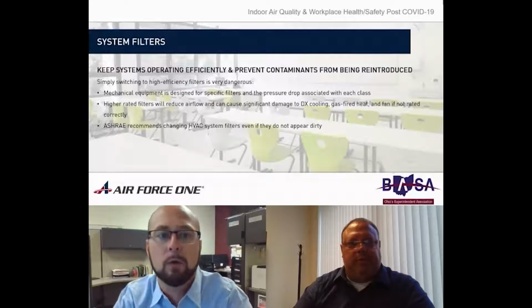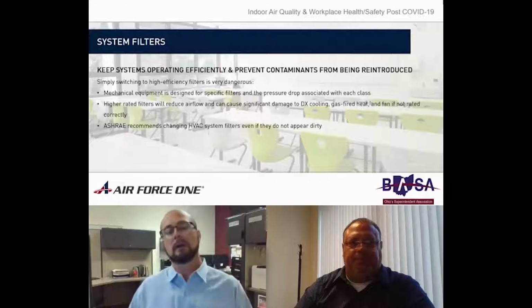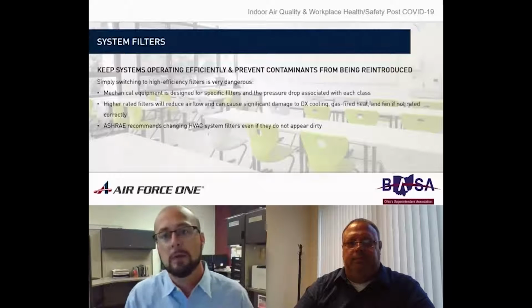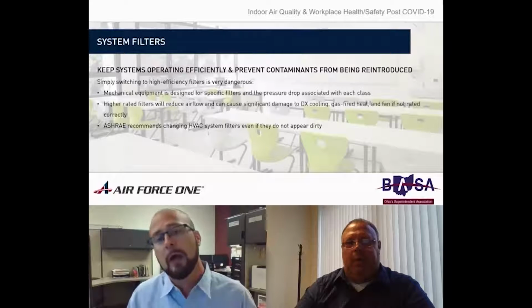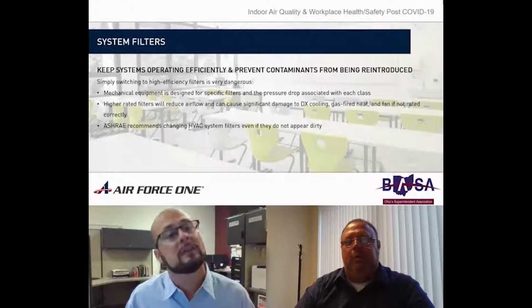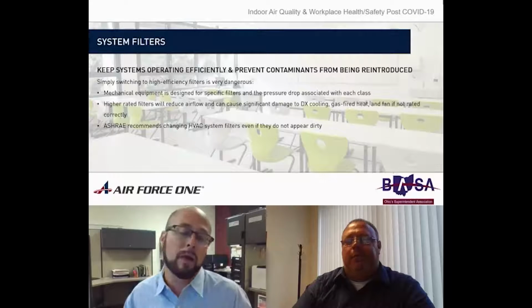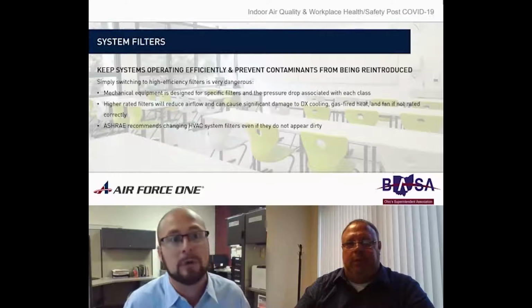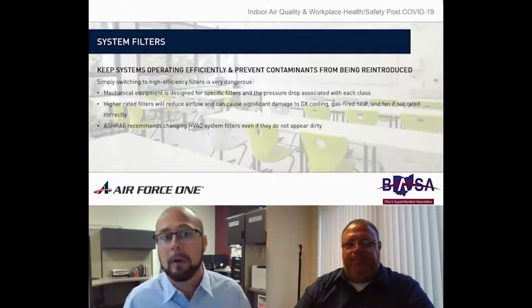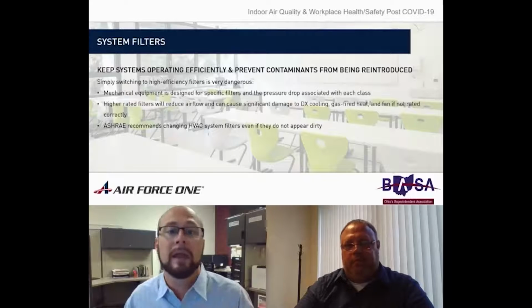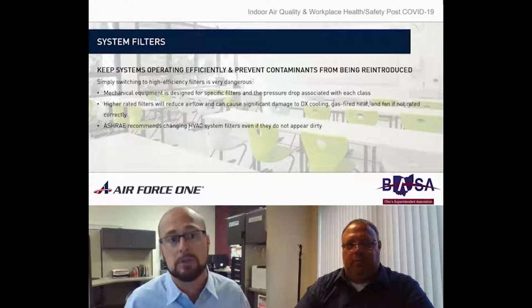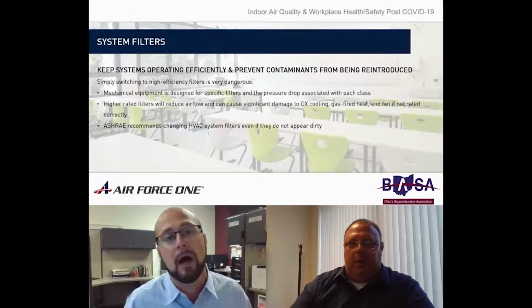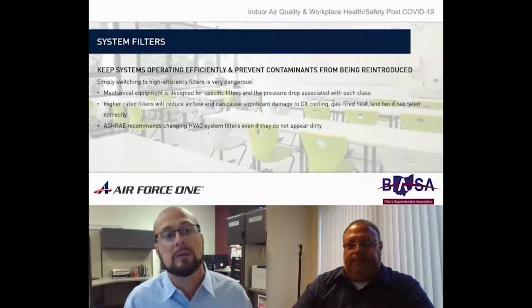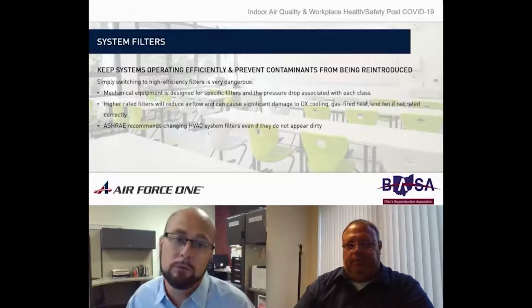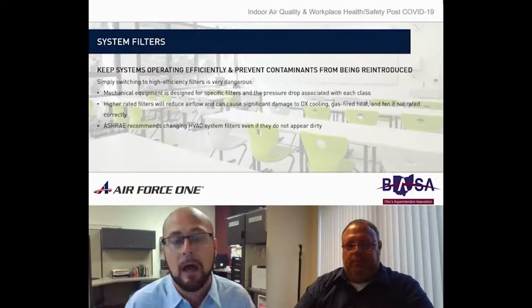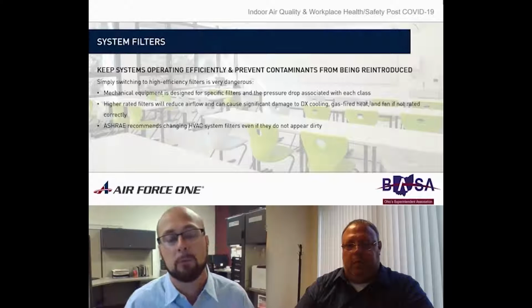More specifically, mechanical equipment is designed for a specific pressure drop associated with each class of filter. If you listen to the CDC and the state of Ohio, they've been recommending high MERV rated filters or even HEPA. Higher rated filters will reduce airflow and can cause significant damage. One thing to keep in mind, especially during these times: even if the filters don't appear dirty, make sure that they're routinely being replaced.